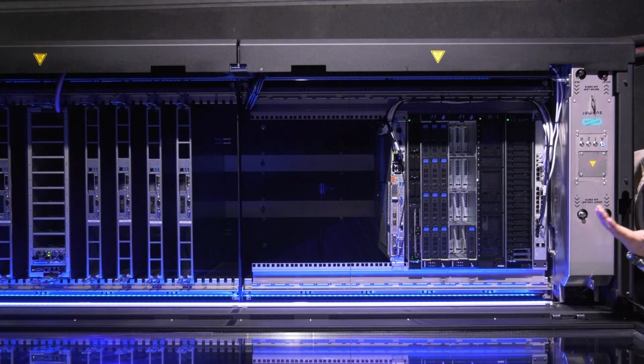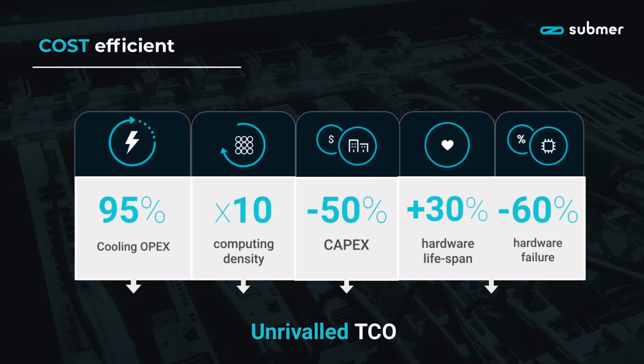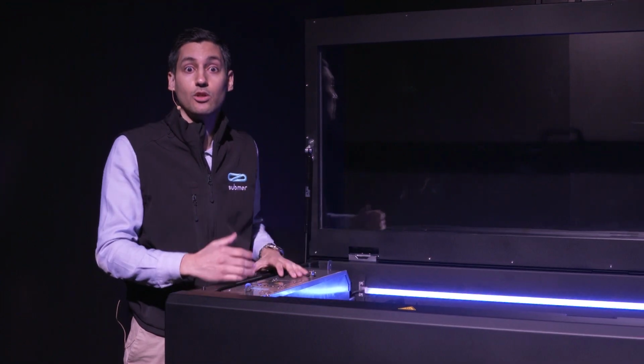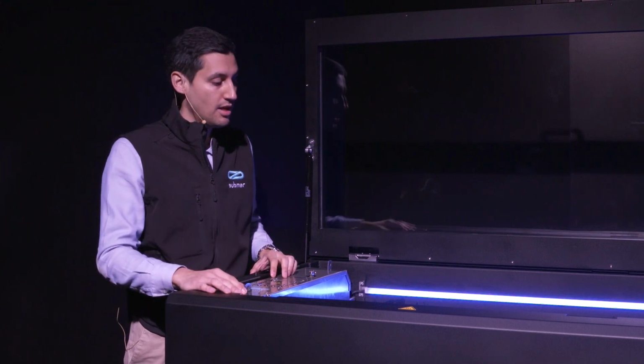This means we can end up saving 85% of the real estate in some cases, and you can have the same logical capacity in these tanks in one single unit compared to 10 to 20 traditional racks. These massive densities allow you to use hyper-convergent hardware and virtualize the logical capacity you'd otherwise need many racks for.